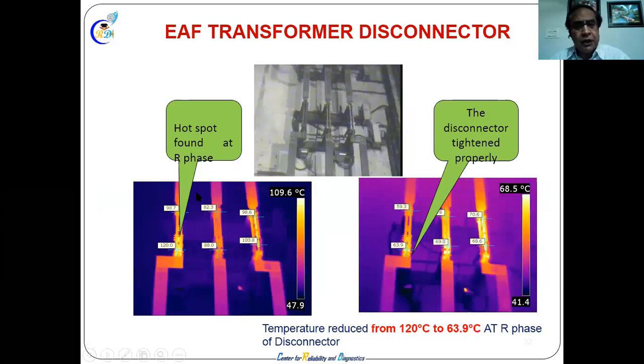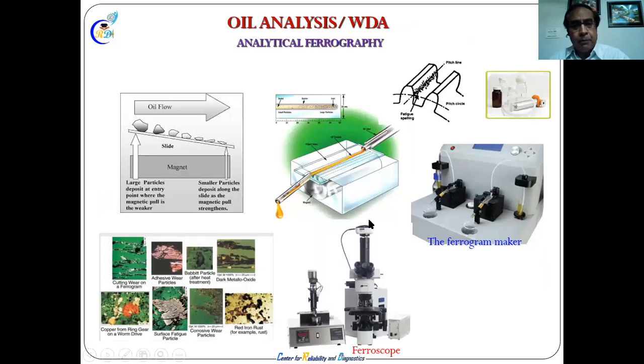Transformer, you see the hotspot here and it was disconnected. After that, this is the original picture and this is the thermal image. Okay, transformer. Oil analysis is a ferrography. You take oil, then you take the oil for properties testing, and you take the oil for machine condition. How do we come to know the machine condition? The oil visits certain places inside the machine. If all those machines have some wear particles, they will come into the fluid, the liquid, and that is tested in a laboratory and we get the analysis.